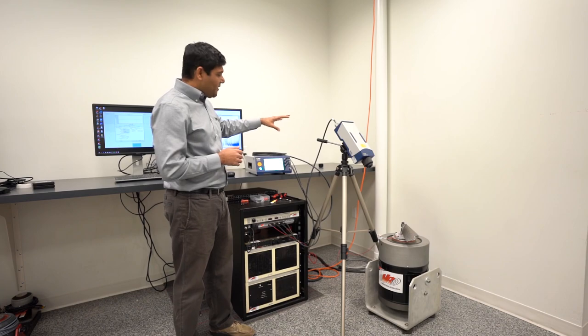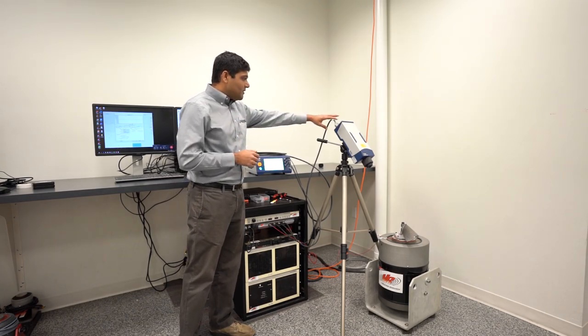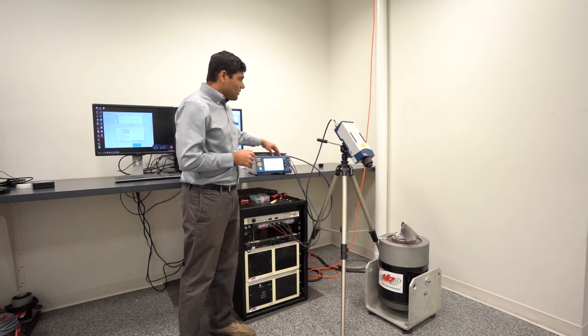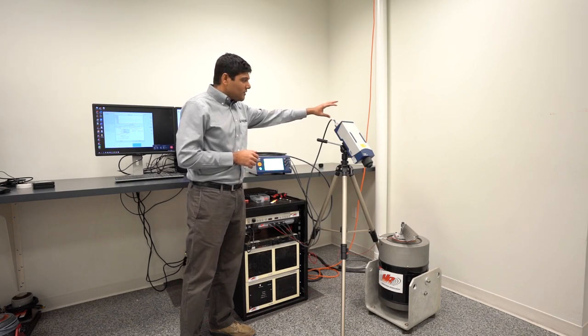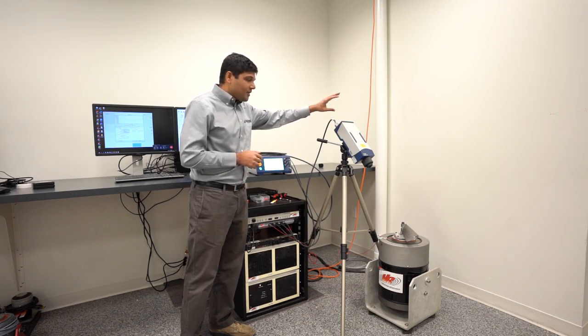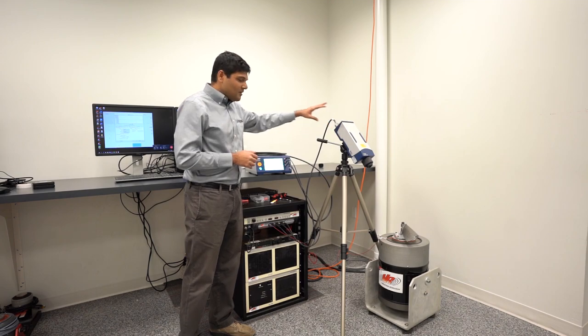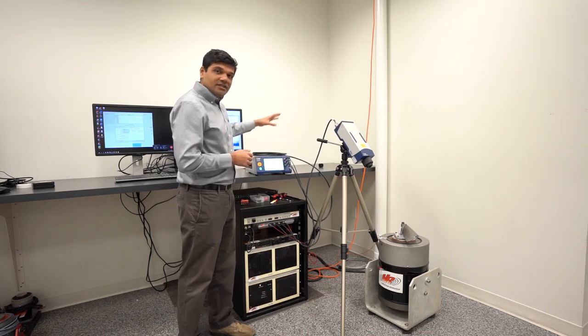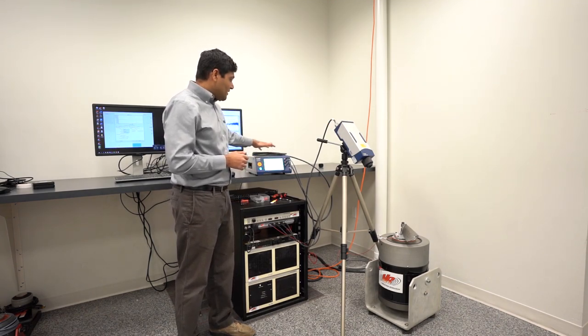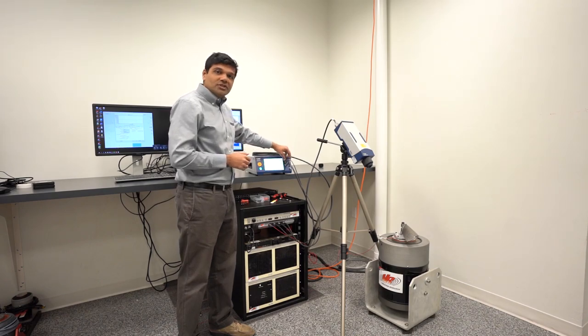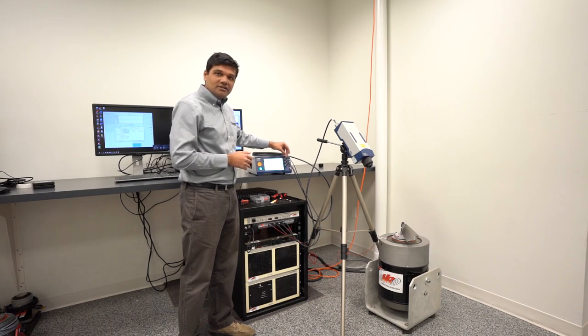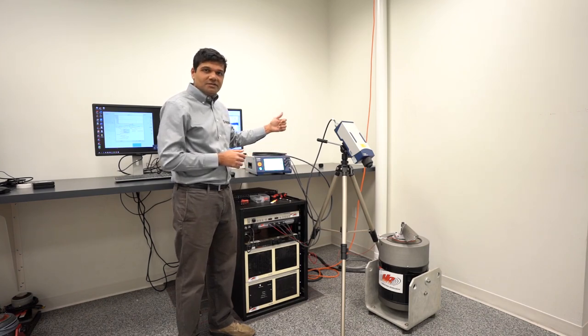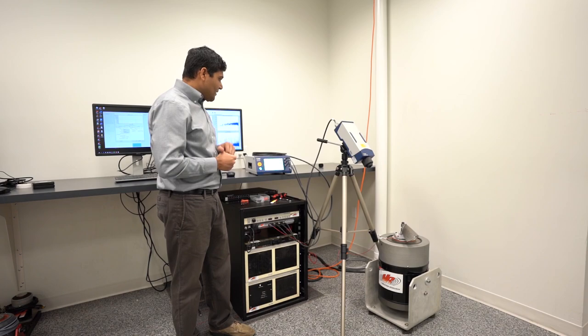There are two components here to the system. We have a sensor head and a controller. So the laser source and the interferometer, everything's built into the sensor. Then the demodulation electronics, everything's demodulated here. And the output is super generic. It's an analog voltage that is proportional to velocity, displacement, or acceleration.